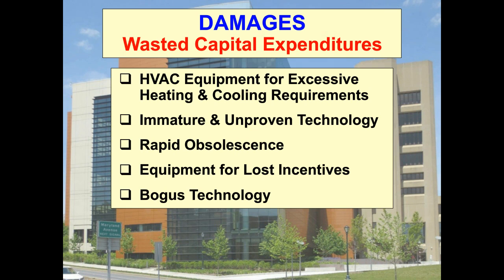The two most expensive and common examples are thermal storage systems and cogeneration systems, and they very commonly fail, either because the equipment is not adequately evolved or because it requires operating skills beyond the capacity of the facility staff. So this leaves the owner with a lot of expensive junk.